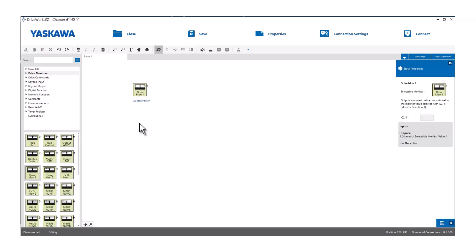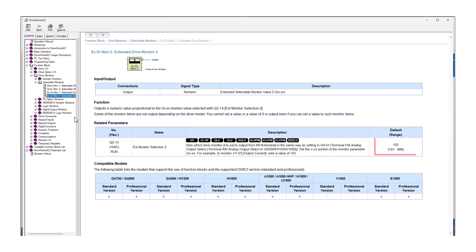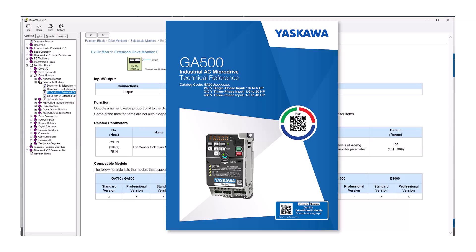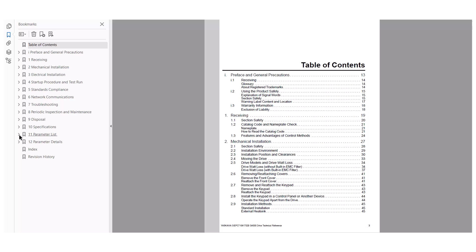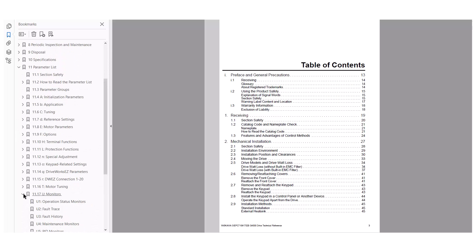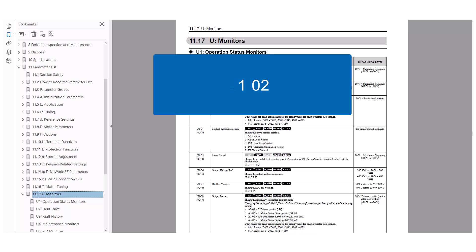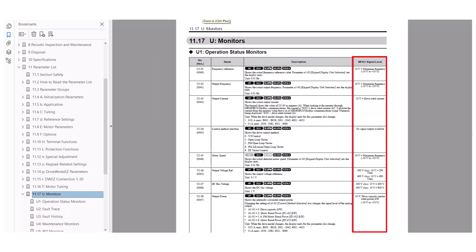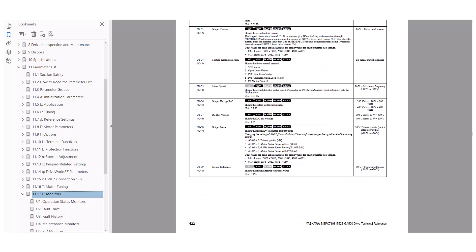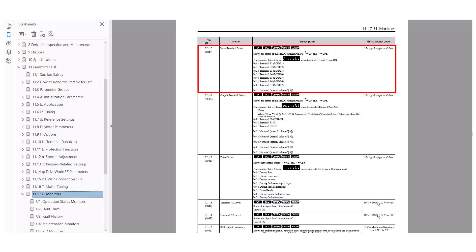There are also extended monitors — the blocks labeled EXDRMON1 and EXDRMON2 — which can be used to output even more variable monitors. The default settings are 102 and 103; 102 represents monitor U102, and the value output by the block will be the output frequency. If you want to output a specific monitor using these blocks, the drive's tech manual is very beneficial. Flip to the parameter listing, generally section 11, to find the parameter list. Anything labeled U is a monitor — drop the U and the dash and put that three-digit number into the Q parameter for that function block. Note that on the right side of the table there is an analog output level column representing the scaling of the monitor. You can only use monitor numbers that have an analog output level listed — for example, you can't use U110 because that's a binary value and you cannot output a binary value with an analog output.